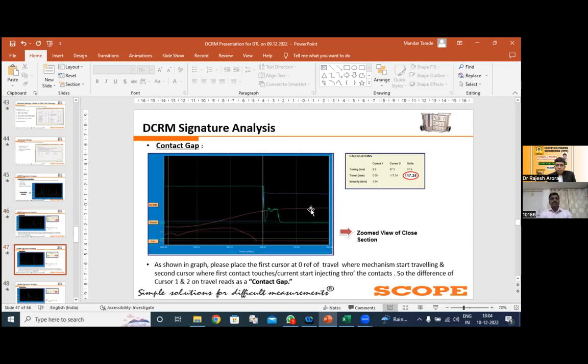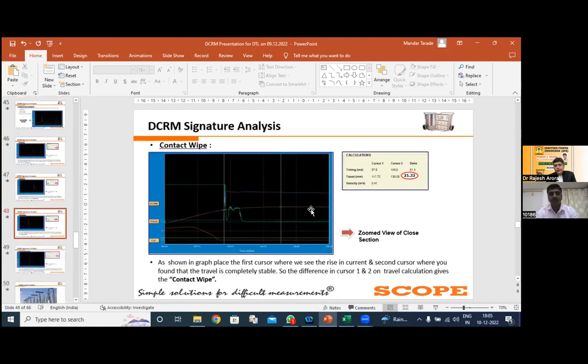Moving ahead to the second parameter, the contact gap. Whenever we need to check the contact gap value, we keep the first cursor as it is, and shift the second cursor to the first contact touch point, where the current starts building. Whenever your arcing contact touches, your current will start flowing. So the delta between the zero travel position and the first contact touch point gives you the value of the contact gap.